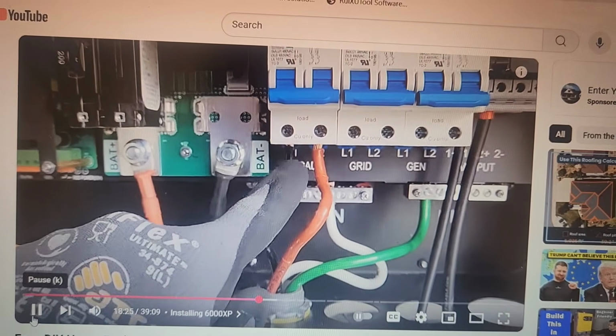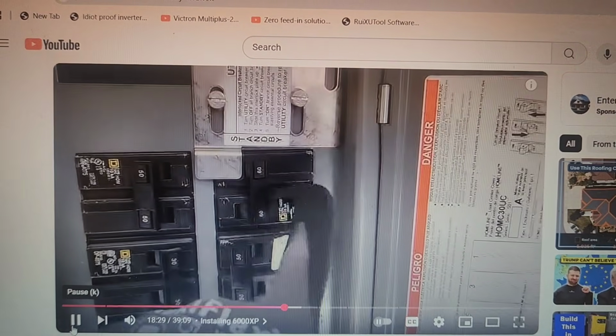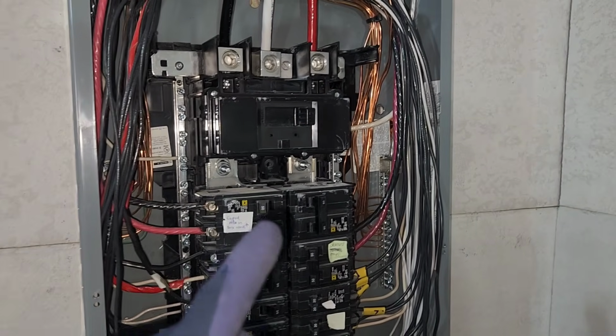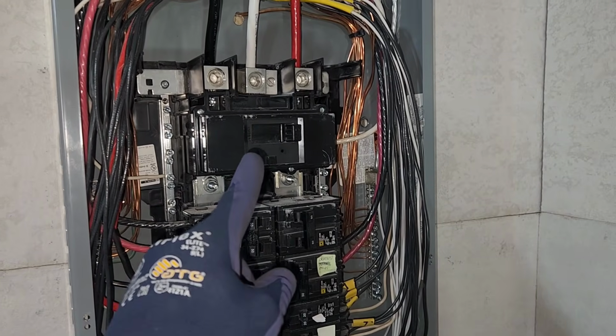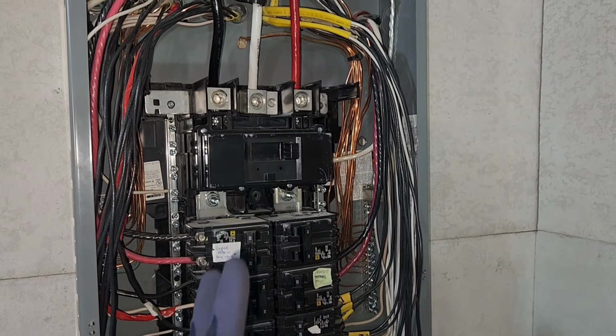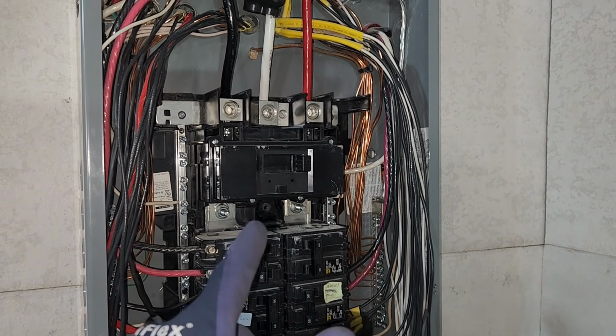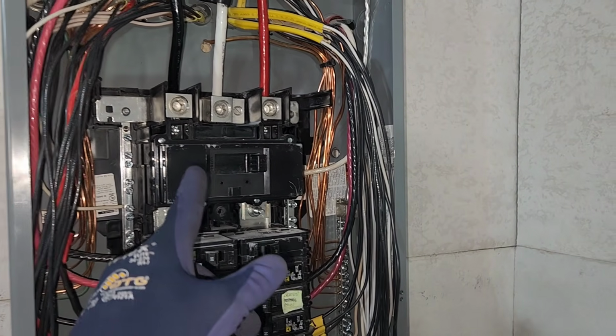This is where my load sends power through here, and it goes into this breaker. The only problem with an interlock kit is you have to have one of these breakers right here to make sure you're not backfeeding and energizing the grid when the linemen are working on the power lines.